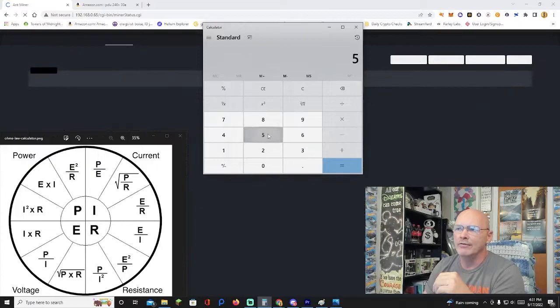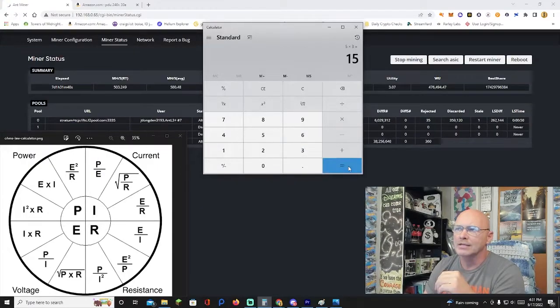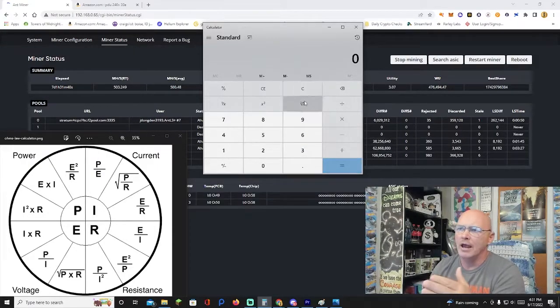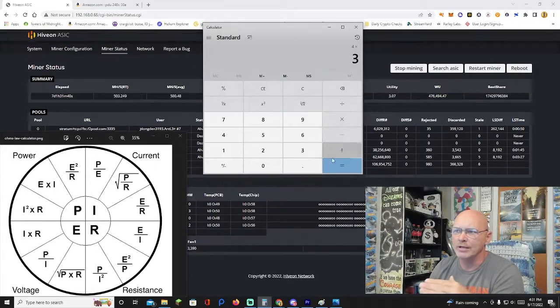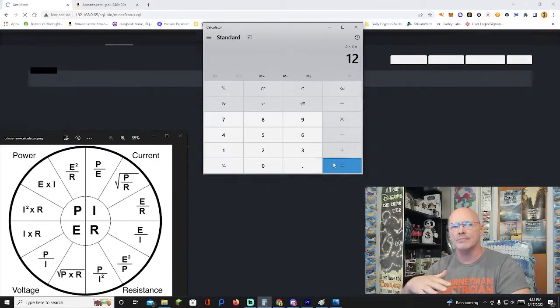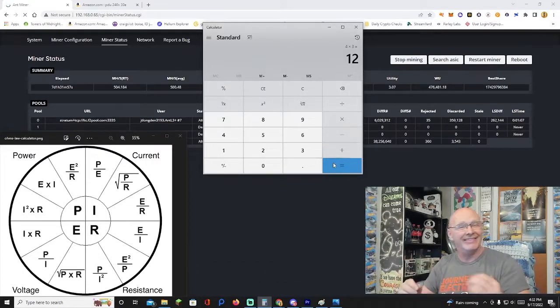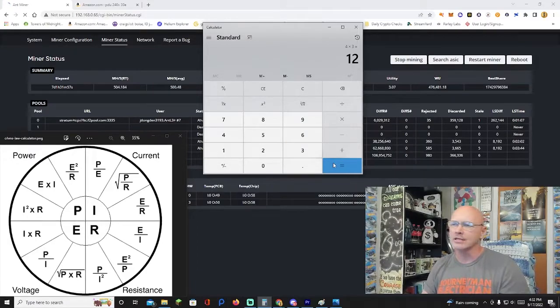So if I go 5 times 3, it's going to give me 15 amps on one, and then 4 times 3 is going to give me 12 amps on the other. Now, that's much more reasonable compared to what I feel safe at. So instead of one 30 amp circuit that I'm right at the breaking point, I'm going to do 2 20 amps and split them 5 and 4. And that'll even give me room to add one more machine to this down the line.